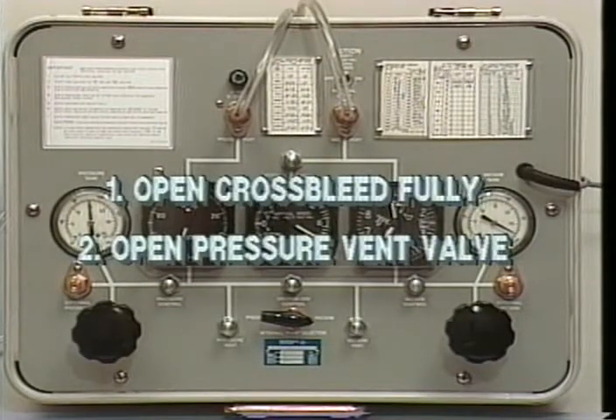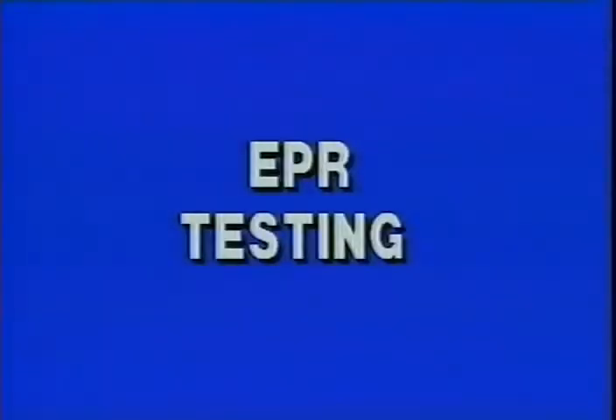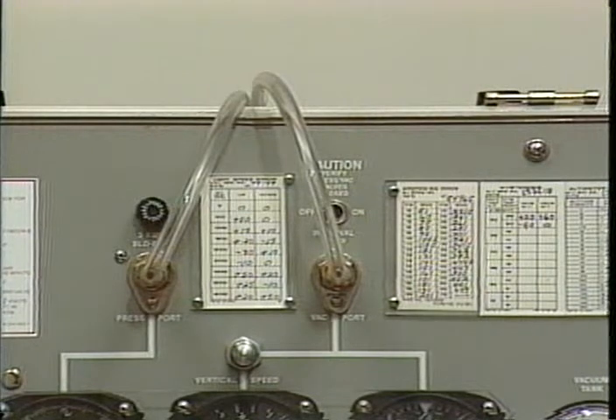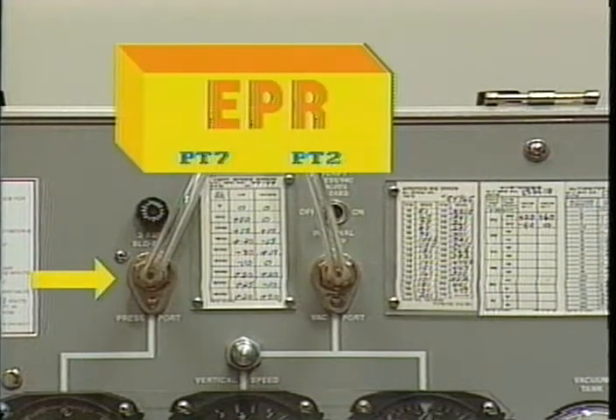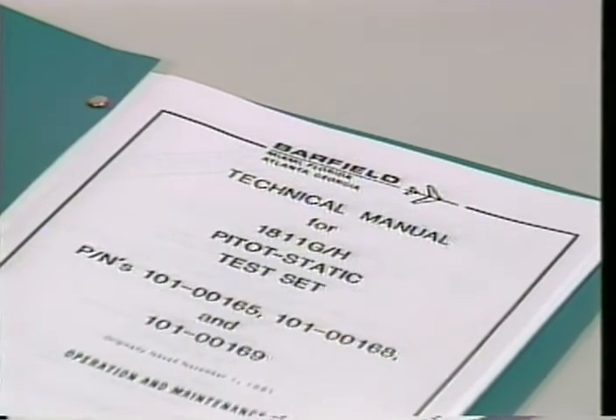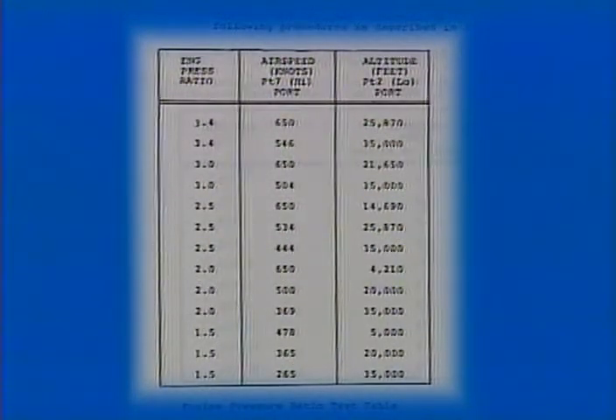As mentioned earlier, this maintains positive pressure, preventing damage to the airspeed indicator diaphragm. You can use the 1811 to test an engine pressure ratio transmitter by using the above procedure combined with the following. First, connect the pressure port to PT7, high port of the EPR unit, and connect the vacuum port to PT2, low port of the EPR unit. The test points are referenced in your aircraft maintenance manual or in our instructional manual. This chart shows some of the common test points with their equivalent airspeed and altitude settings.